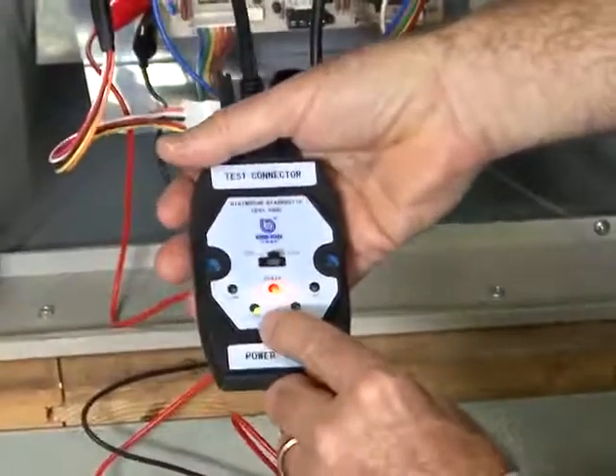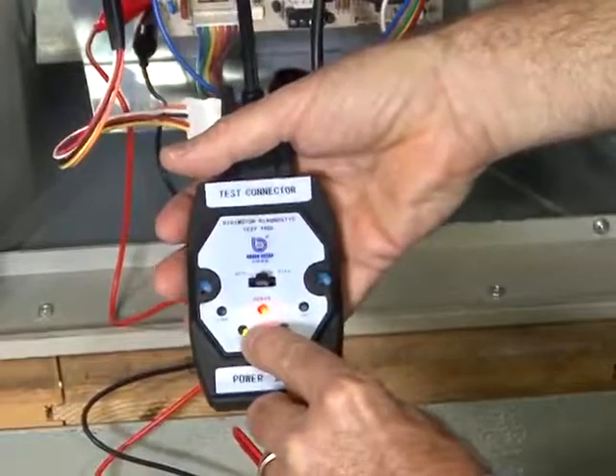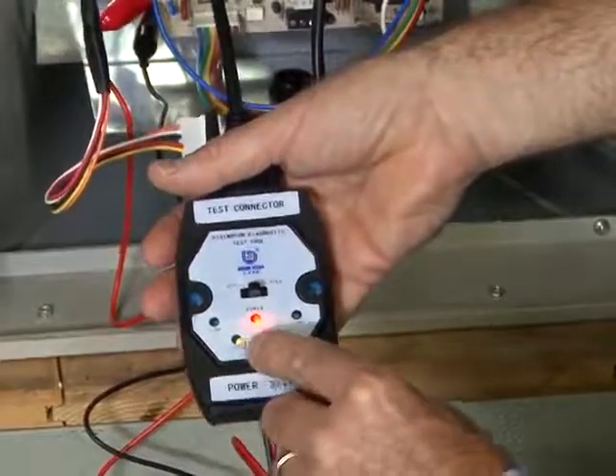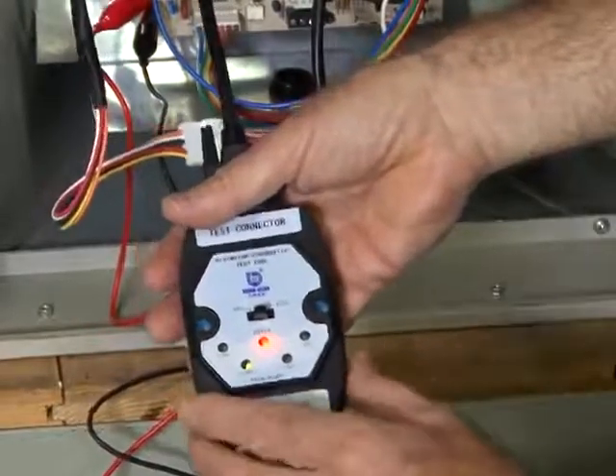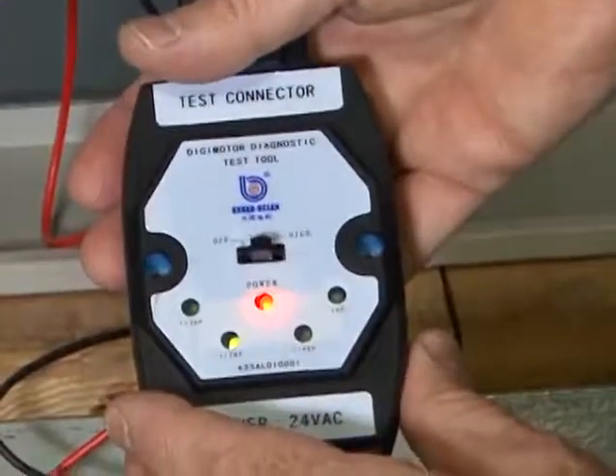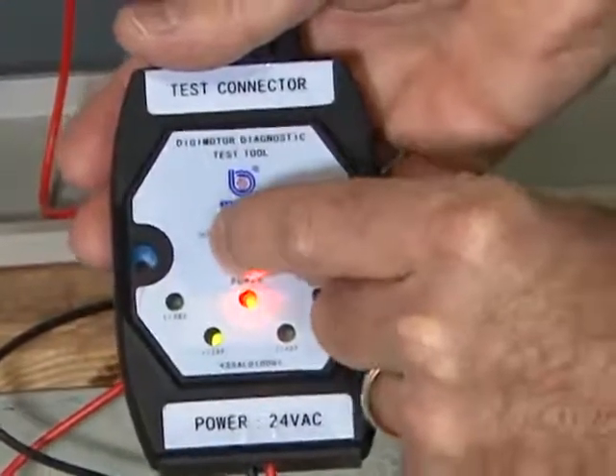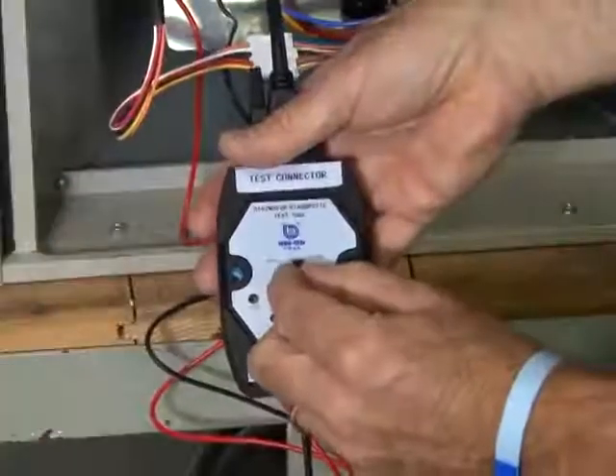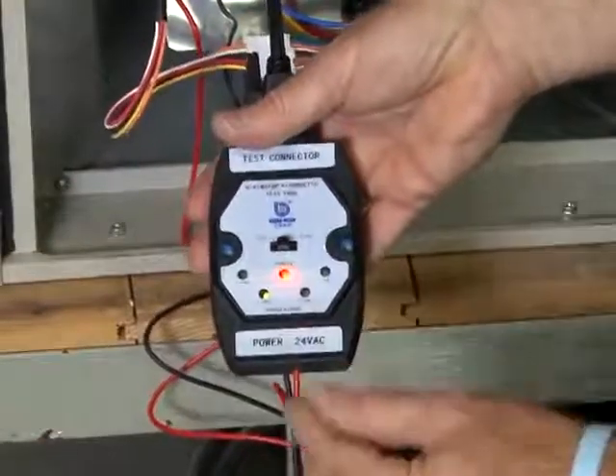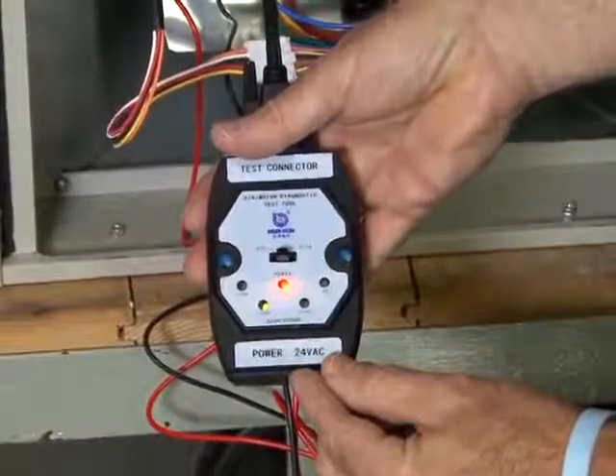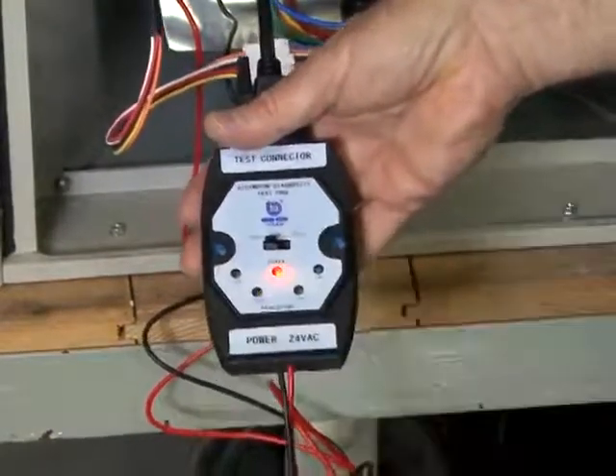If I turn on the power, the broad ocean motor tester identifies this as a 1/2 horsepower motor, and my motor did come on. I can now cycle the motor up to high speed with my tester. Back down to low, and then cycle it to off.